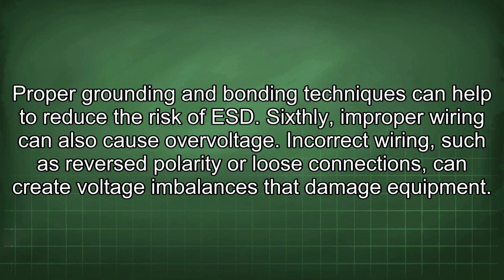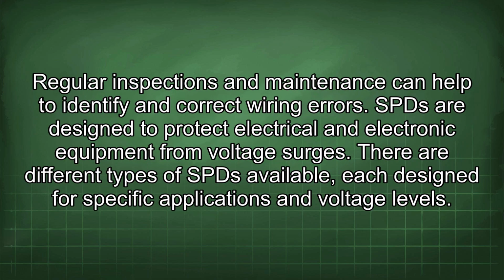Sixthly, improper wiring can also cause overvoltage. Incorrect wiring, such as reversed polarity or loose connections, can create voltage imbalances that damage equipment. Regular inspections and maintenance can help to identify and correct wiring errors.